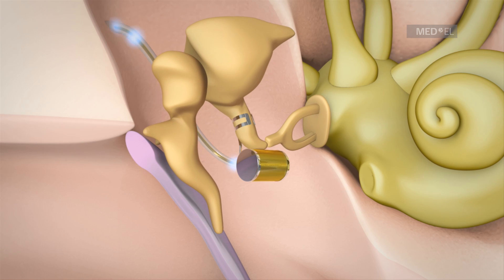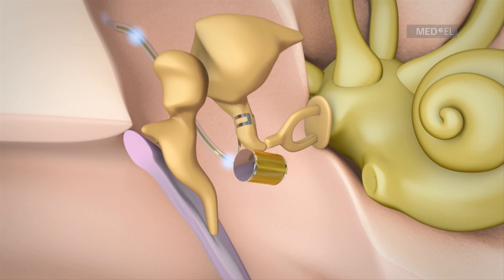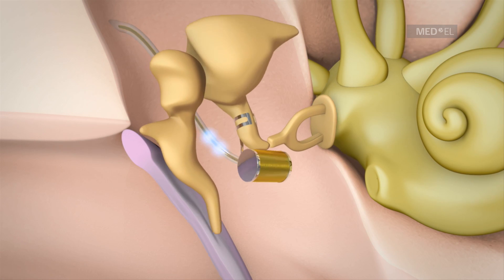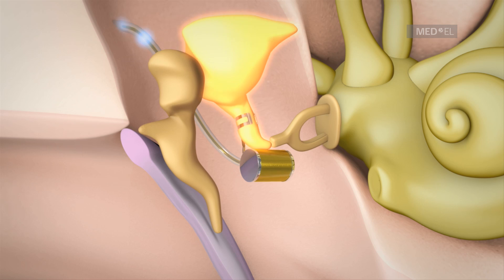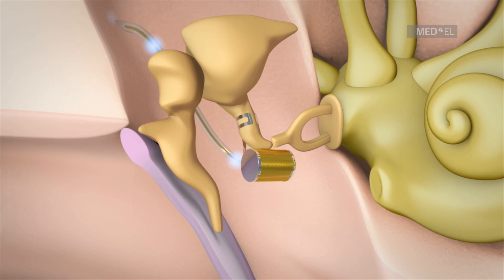The FMT has a frequency range of up to 8,000 Hz. The versatility of the FMT has led to a variety of surgical applications known as vibroplasty. The incus vibroplasty, for example, involves affixing an FMT to the incus. This procedure is a treatment for sensorineural hearing loss.